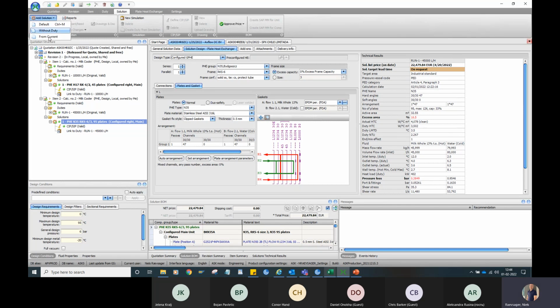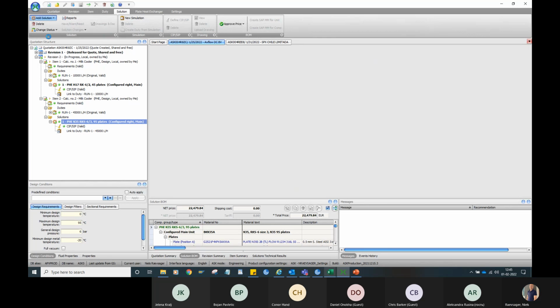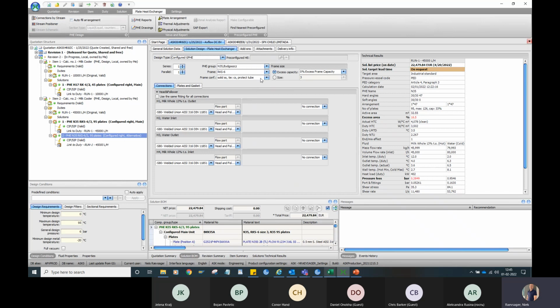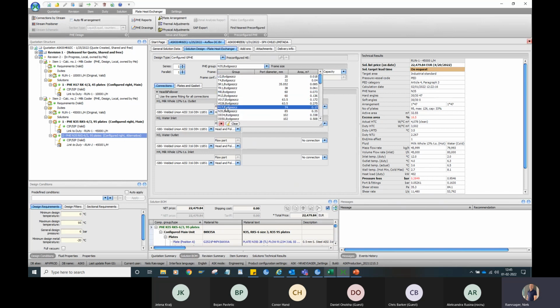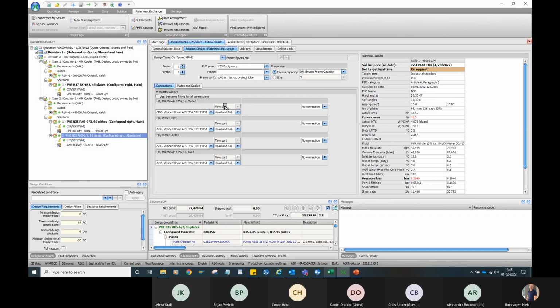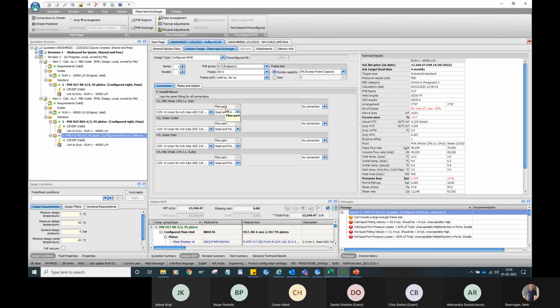Add solution, and I say from current. Then I change it to a H17. Then obviously a frame size, I cannot locate a frame large enough. I can only have 57 plates in the largest 6-bar frame. So first thing I have to do is change to a 10-bar frame, RKS 10.